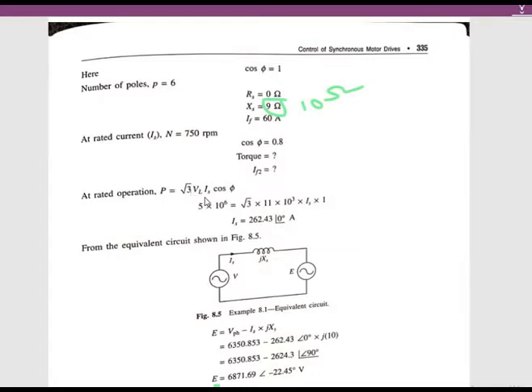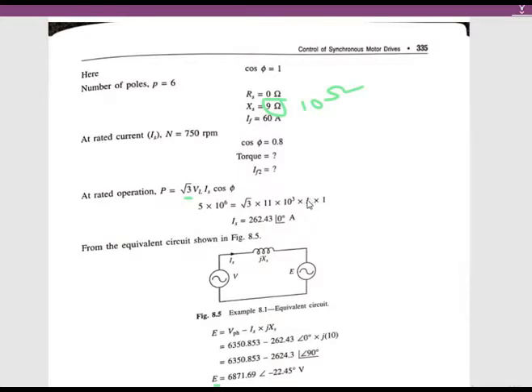Mechanical power equals input power: P = √3 · VL · IL · cos(φ). Substituting 5×10⁶ = √3 × 11×10³ × IS × cos(φ), with cos(φ) = 1 at UPF, we calculate IS = 262.43 amperes at an angle of 0 degrees. This is the rated armature current at which the machine is actually running.